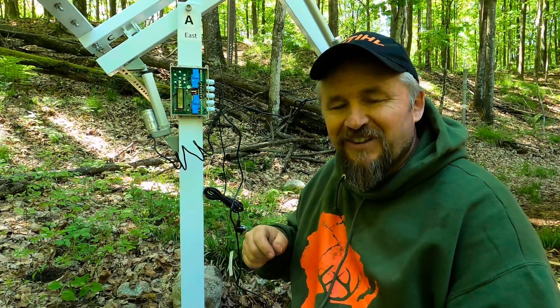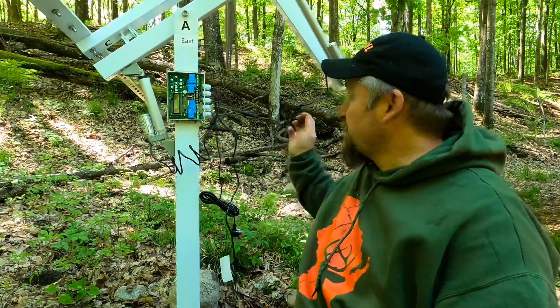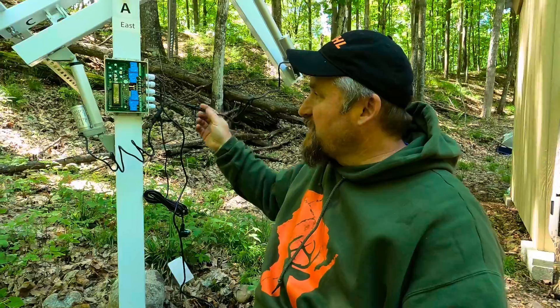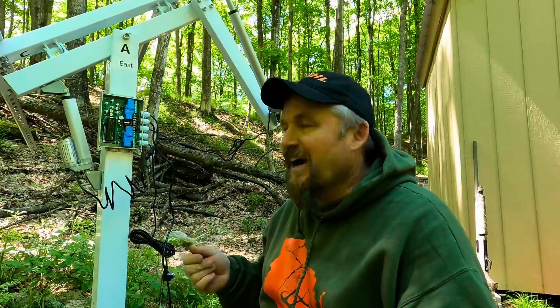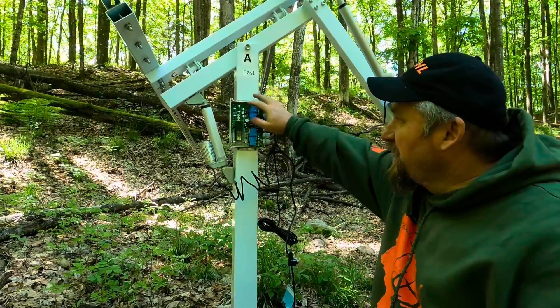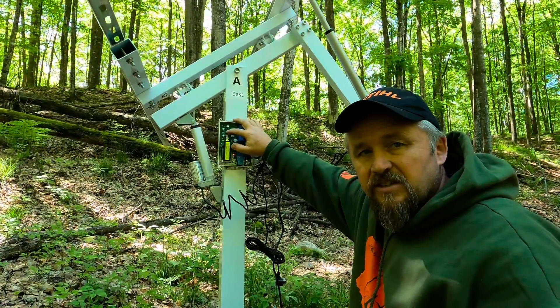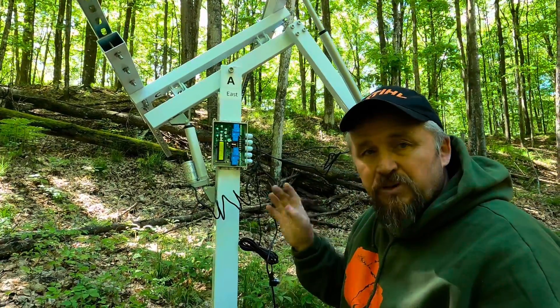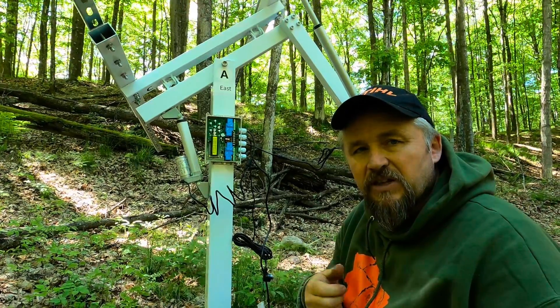I'm going to give you a close-up — it won't look real professional. This actuator controls the east and west. I followed it back to the control box and right at the tip of my finger there is a black wire and a red wire. Those control the east and west, and what I did is switch those. The red wire was originally on the bottom, the black wire was on top. I just switched those two around. Now when I hit my controls to go east, the panels travel east, and when I hit west, the panels travel west.